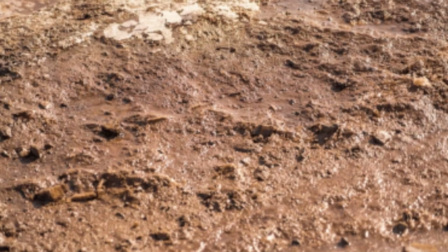4. Compression sedimentation. Also known as Type 4 sedimentation, this happens when the concentration of particles is so high that the lower layers are compressed by the weight of the particles above. This process is common in the final stages of sludge thickening and dewatering. Examples: sludge compaction in wastewater treatment facilities. Settling of tailings in mining operations.